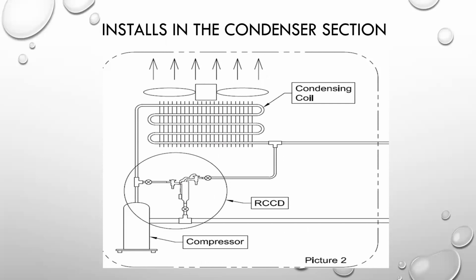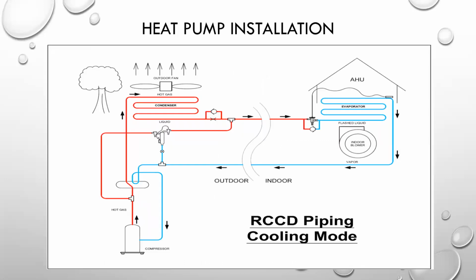One thing that needs to be known and said all the time: this ball valve right here, between the discharge of the valve and the suction T, has to be in place. It can be installed in heat pumps. Critical point there is look where the suction line's connected. It's between the reversing valve and the indoor coil. If you connect it between the reversing valve and the compressor, whenever you're trying to heat in the wintertime, the colder it gets outside, the less heat you're going to have because it's going to keep unloading and taking the energy away from the house.